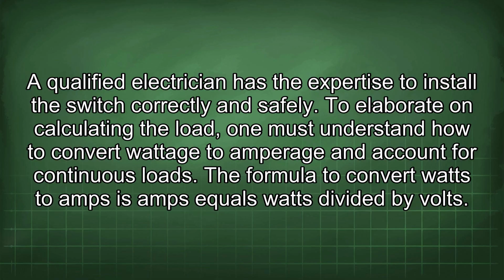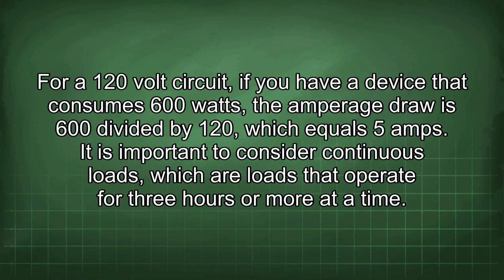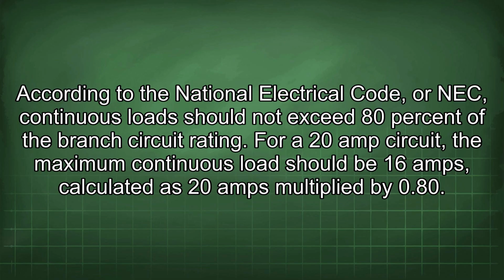To elaborate on calculating the load, one must understand how to convert wattage to amperage and account for continuous loads. The formula to convert watts to amps is amps equals watts divided by volts. For a 120-volt circuit, if you have a device that consumes 600 watts, the amperage draw is 600 divided by 120, which equals 5 amps. It is important to consider continuous loads, which are loads that operate for 3 hours or more at a time. According to the National Electrical Code, or NEC, continuous load should not exceed 80% of the branch circuit rating. For a 20 amp circuit, the maximum continuous load should be 16 amps, calculated as 20 amps multiplied by 0.80.